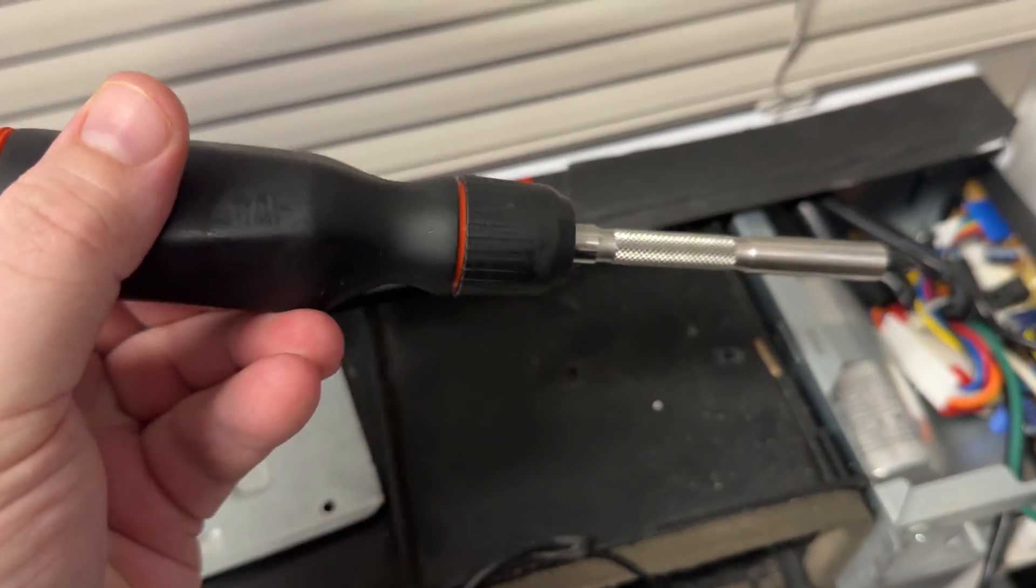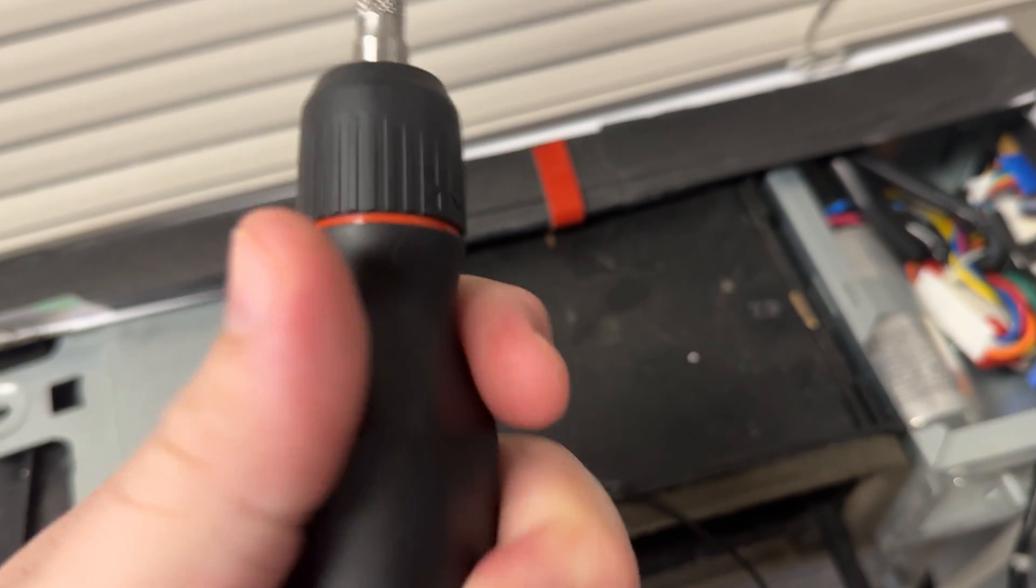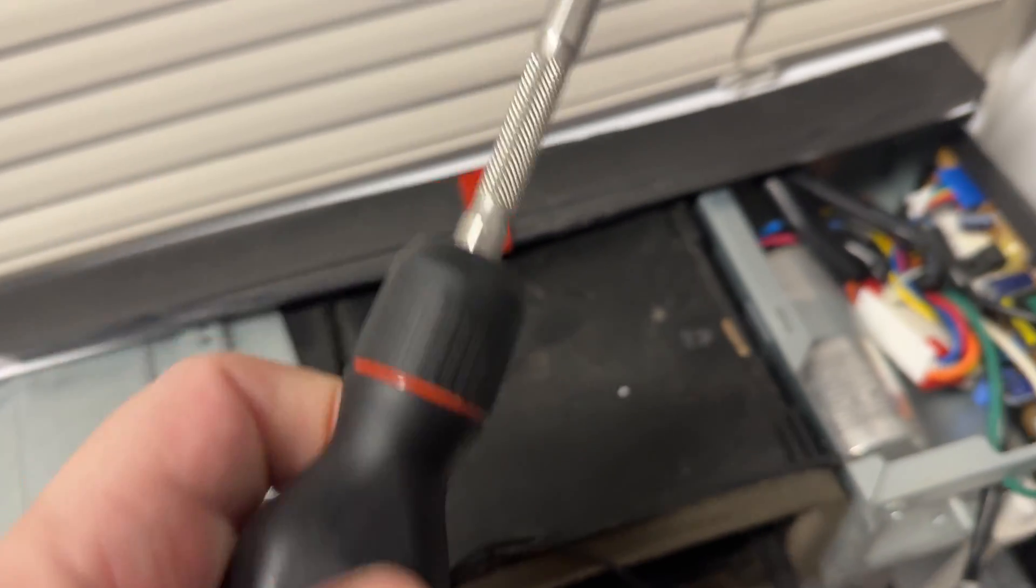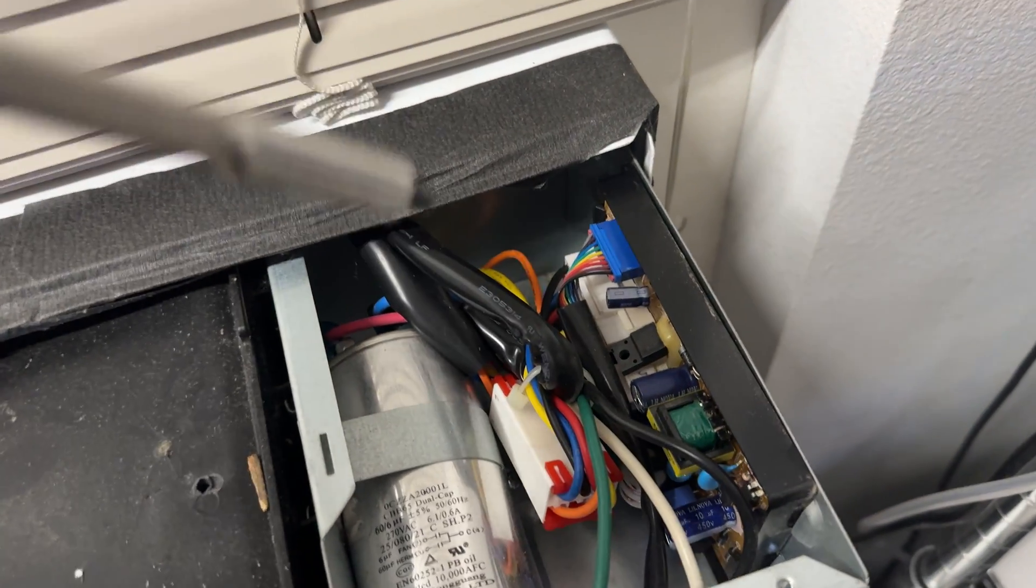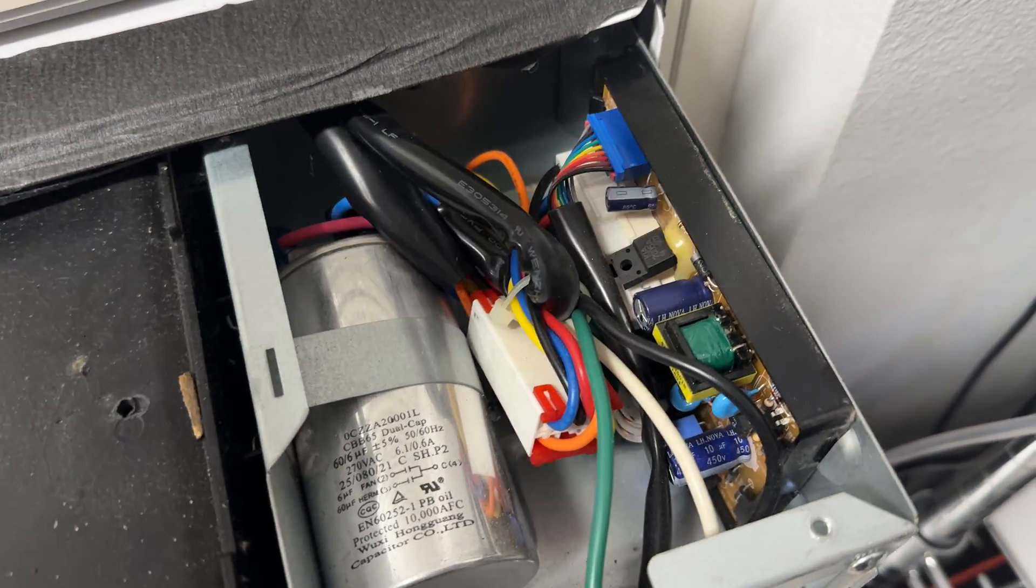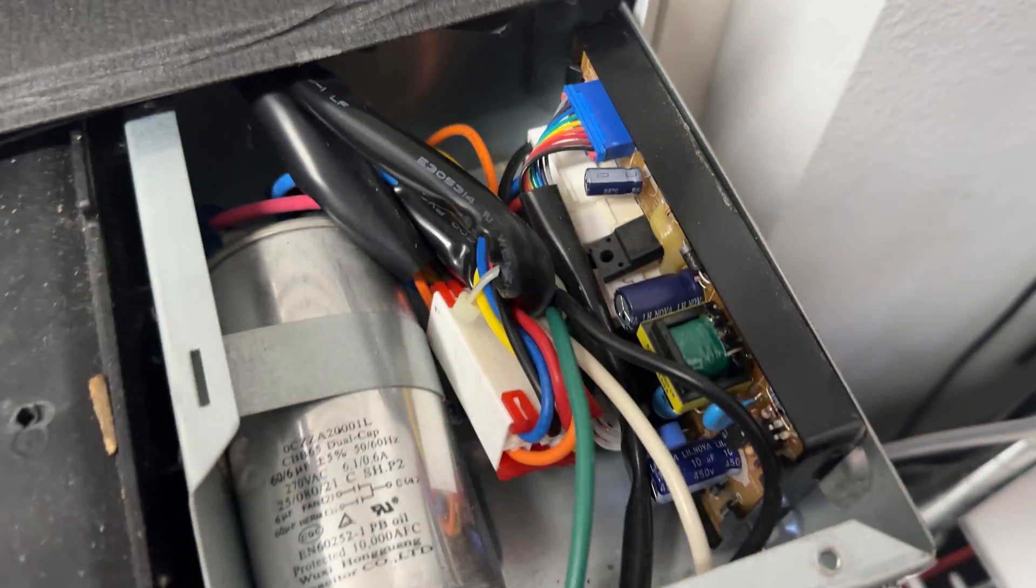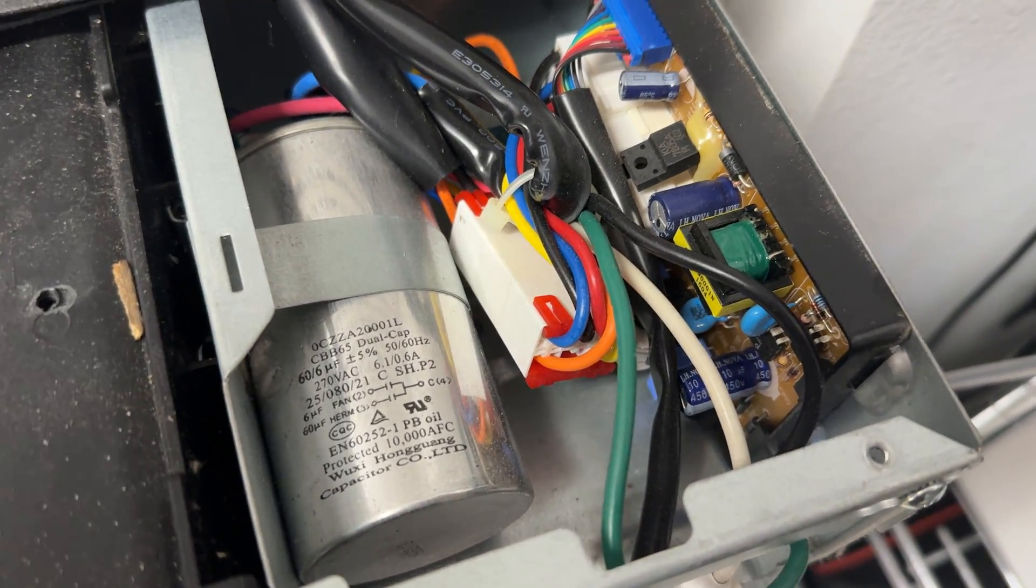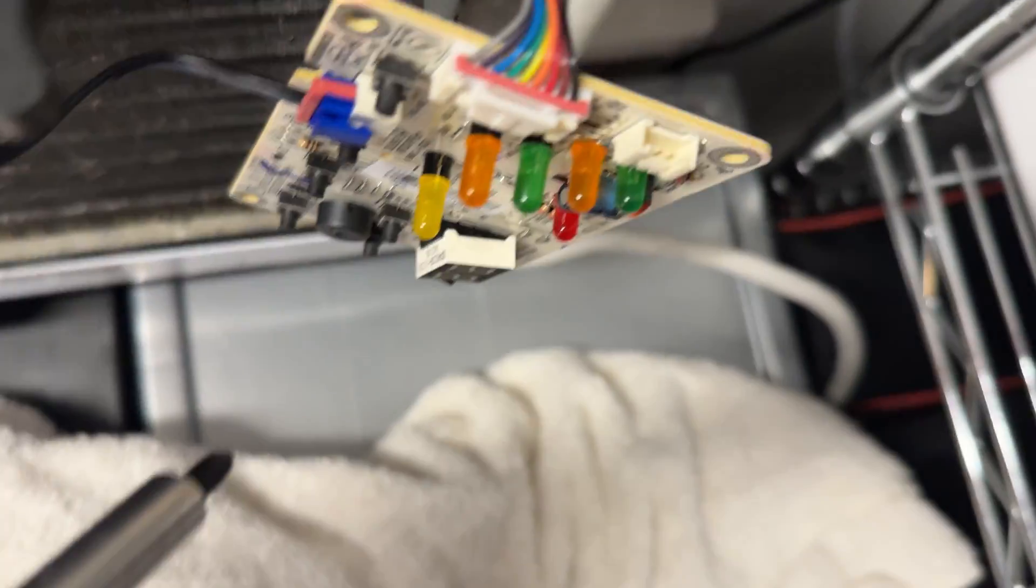I think that's the relay for the compressor. What I'm gonna do is take my LTX screwdriver - hopefully it's insulated, I mean it feels insulated - and I'm gonna reach down there and just bang on that relay and see if I can free it up because it is frozen.